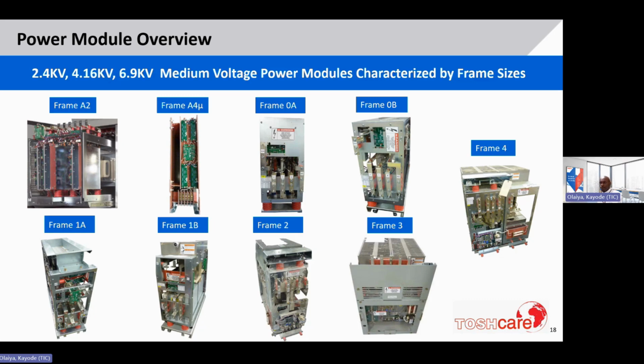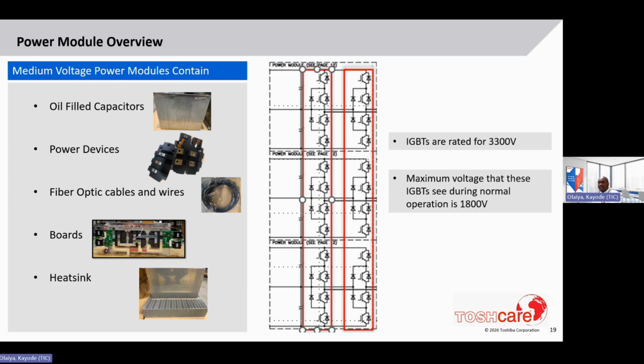You have the frame 2, which goes up to 3,000 horsepower. Frame 3 up to 3,000, and then the frame 4 up to 6,000. Notice that the higher the horsepower, the bigger the power module is. And mostly the components are the same in each of these. And I'll go over these components.